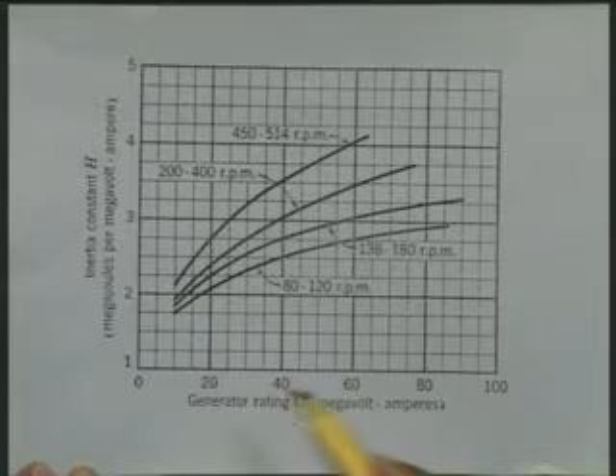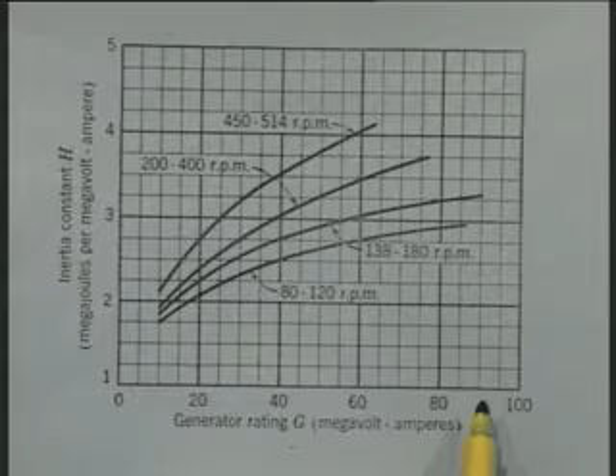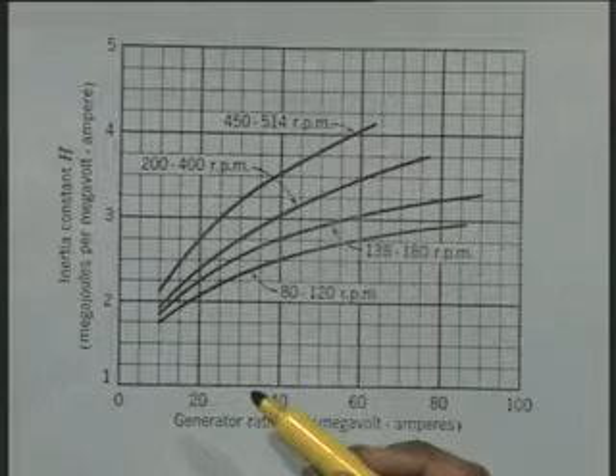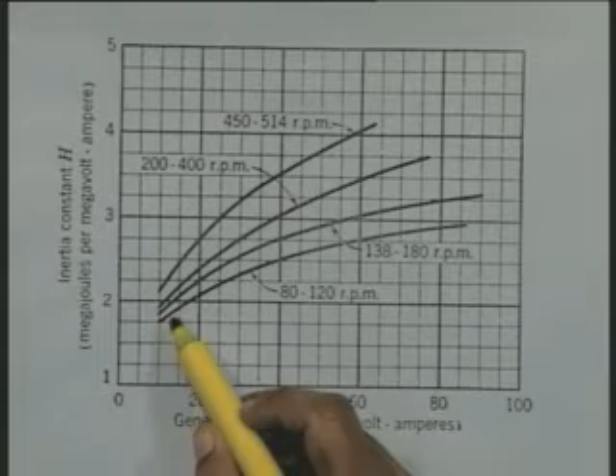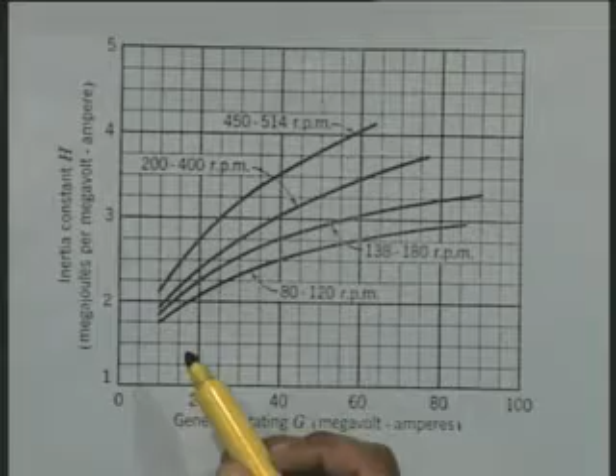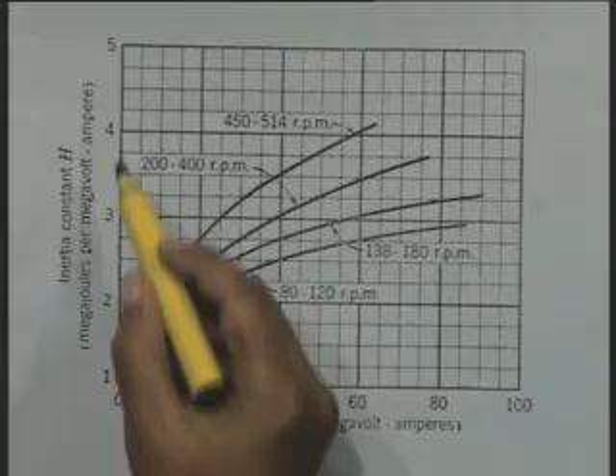Now, this graph shows the characteristic values of inertia constant H for a hydro generator. Again, on the x axis we have marked the rating of the machine in MVA, and on the y axis the inertia constant H in megajoules per MVA. Here you see that machines having different speeds do have different values of inertia constant H. It increases with increase in the MVA rating of the machine, but still you can see it lies in a certain range.